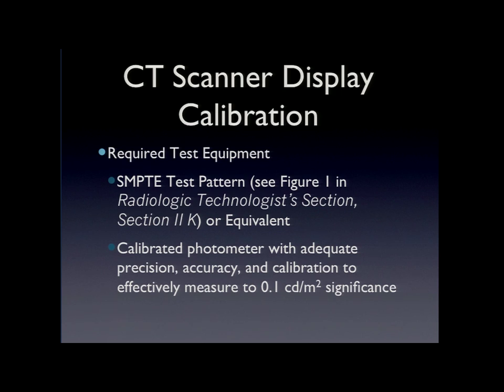What you need to do is just evaluate the viewing conditions of that. A SMPTE pattern is typically used. It's on most of them, not all of the CT scanners. If not, the physicist should try to get the pattern added.